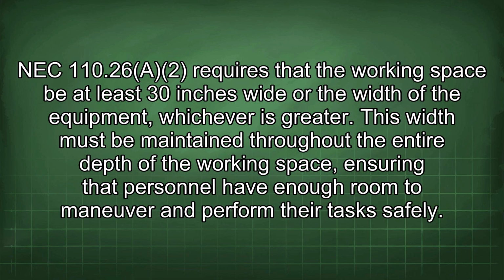NEC 110.26(A)(2) requires that the working space be at least 30 inches wide or the width of the equipment, whichever is greater. This width must be maintained throughout the entire depth of the working space, ensuring that personnel have enough room to maneuver and perform their tasks safely.